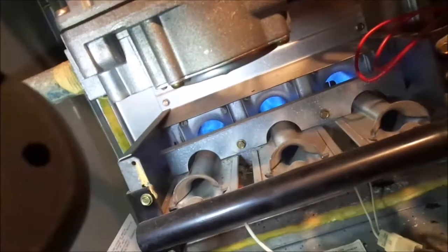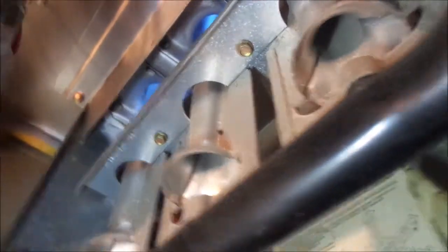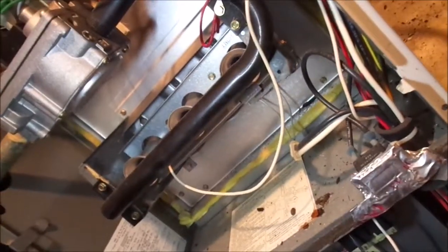I don't smell anything burning now except for that gas. Nice blue flame in there. Now there's a flame sensor in there — that flame sensor could be checked. This white wire, that little electrode in there — those things get dirty sometimes, you gotta clean those off. Dollar bills are a cleaning tool for those; definitely don't wanna use sandpaper, just wipe them off basically. That inducer motor smells and sounds a little loud, but maybe that's the way it's supposed to be.